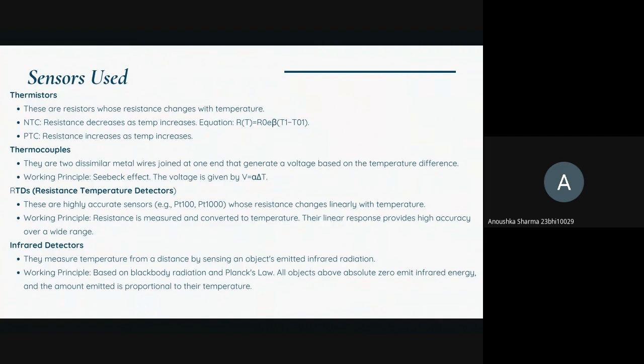Then it comes to the resistance temperature detectors. These are highly accurate sensors whose resistance changes linearly with temperature. The working principle is that resistance is measured and converted to temperature. Their linear response provides high accuracy over a wide range. Now comes the infrared detectors. These measure temperature from a distance by sensing an object's emitted infrared radiation. The working principle is based on blackbody radiation and Planck's law. All objects above absolute zero emit infrared energy, and the amount emitted is proportional to their temperature.